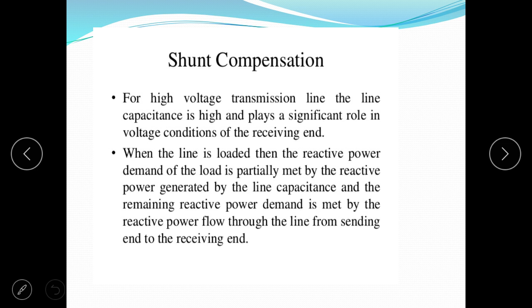Now the second method of compensation is shunt compensation. In shunt compensation, a capacitor is connected in parallel with the transmission line. For a high voltage transmission line, the line capacitance is high and plays a significant role in the voltage condition of the receiving end. When the line is loaded, the reactive power demand of the load is partially met by the reactive power generated by the line capacitance, and the remaining reactive power demand is met by the reactive power flow through the line from sending end to receiving end.